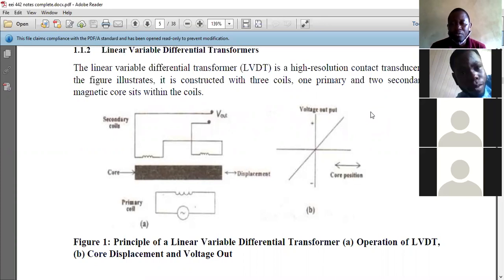The LVDT is made up of 3 coils, and it's a high resolution contact transducer. It has 1 primary coil and 2 secondary coils. The 2 secondary coils are connected in a special way so that you could have addition of the voltage or subtraction. You could have positive voltage at the output or negative voltage at the output. The transformer has a core, and the core is capable of moving linearly.